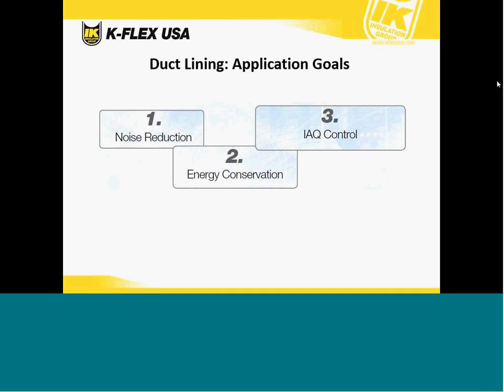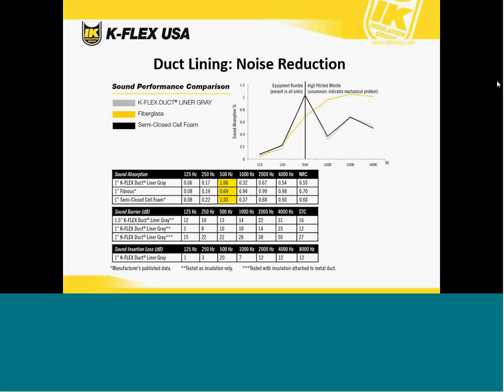Beyond chilled water, we're going to look at the next application, which is duct lining. This is a little different because duct liner is typically more of an acoustic material as opposed to a thermal material. I'll get into that here in a second. As mentioned, duct lining is primarily specified to reduce noise and not to be a thermal material.